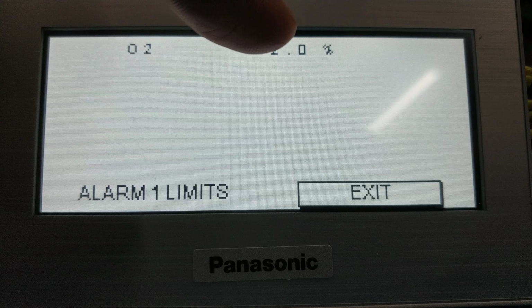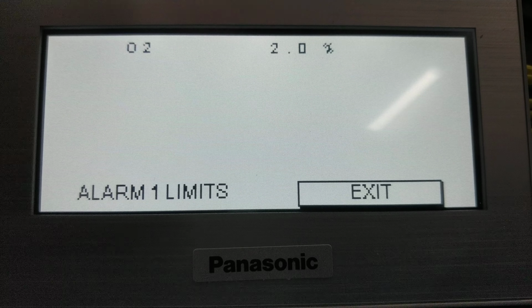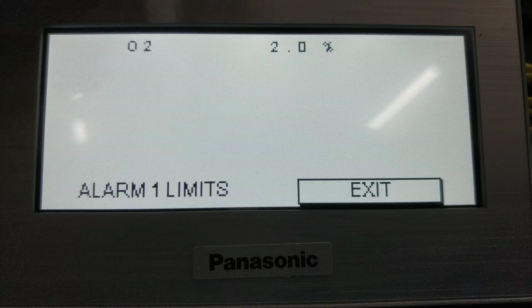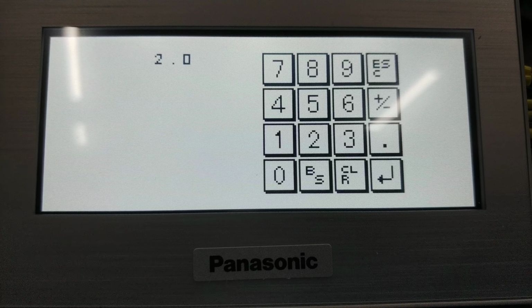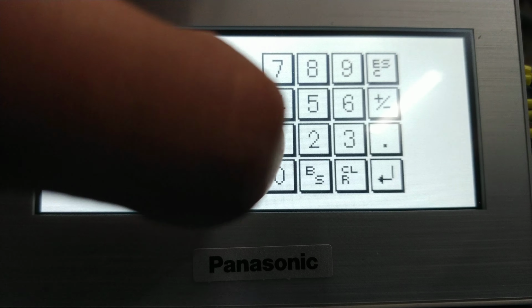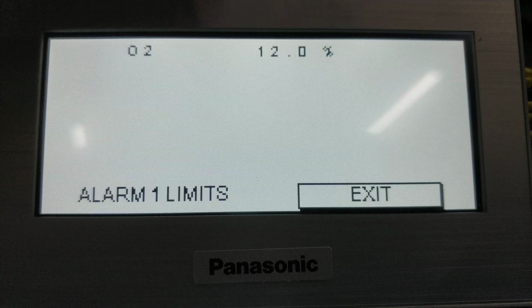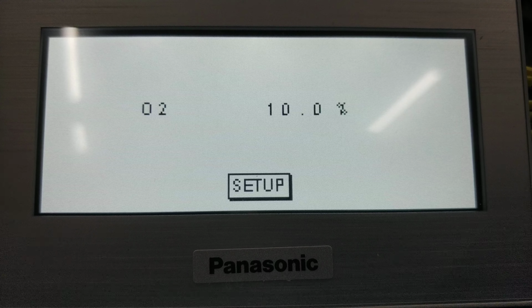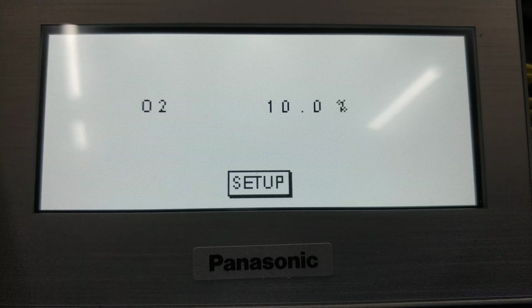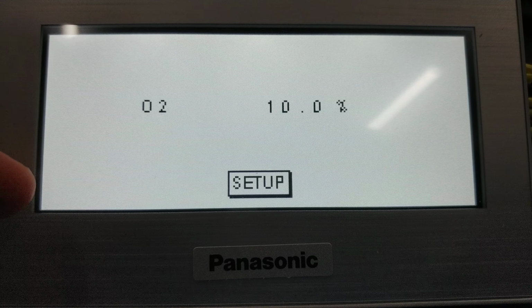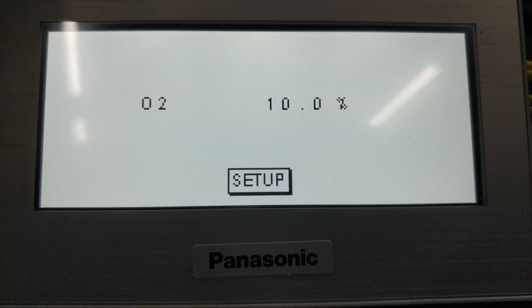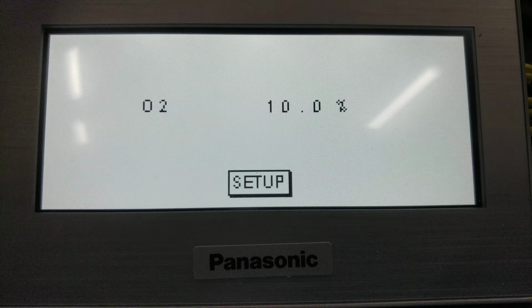So I'm going to select alarm 1, and as you can see, it's been set to 2%, so we want to change that. Let's say, I don't know, 12%. So I'm going to set that to 12%, and enter. So now it's set to 12%. Exit, exit, exit. Okay, so now you see we're running 10%. We're no longer getting the gas alarm. It's gone now. And subsequently, you can just go and change it higher or lower, depending on what you need.